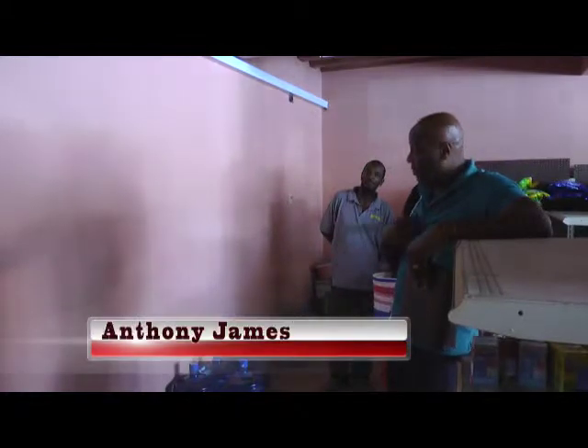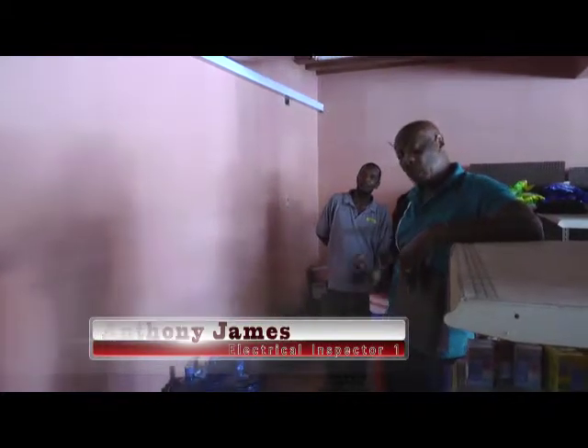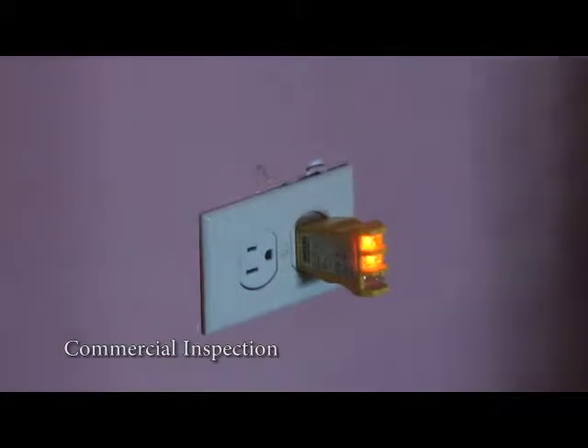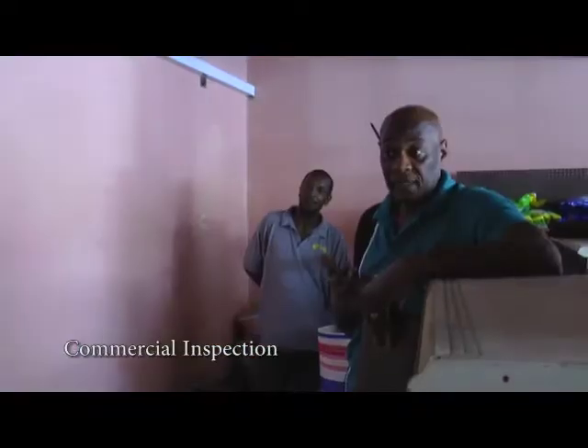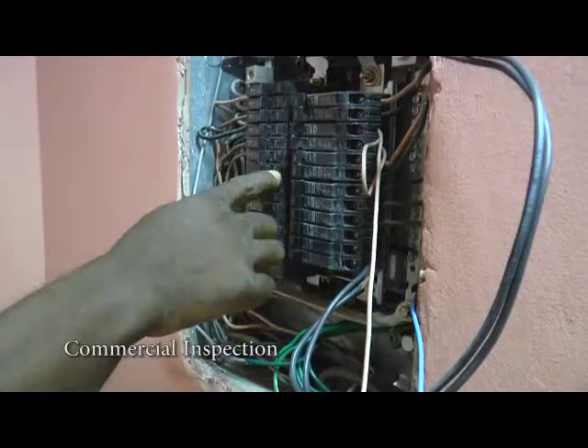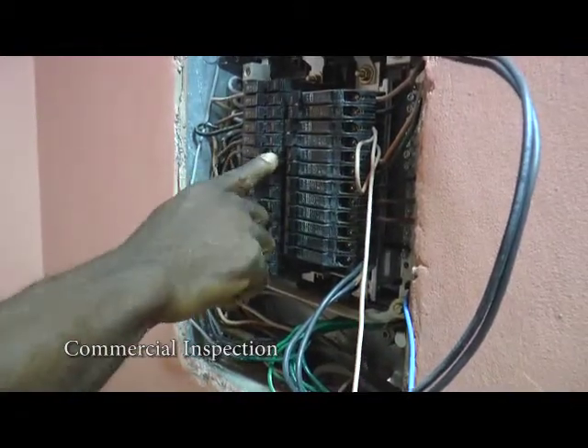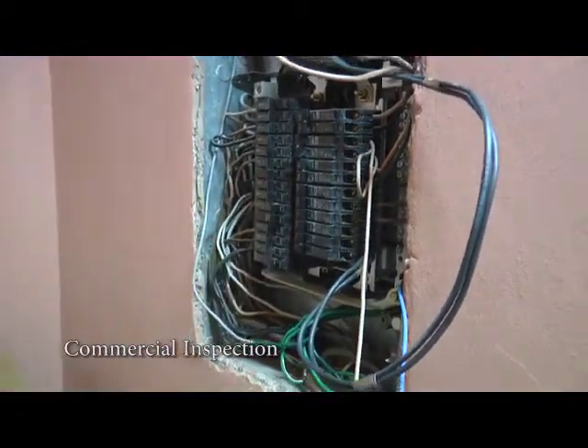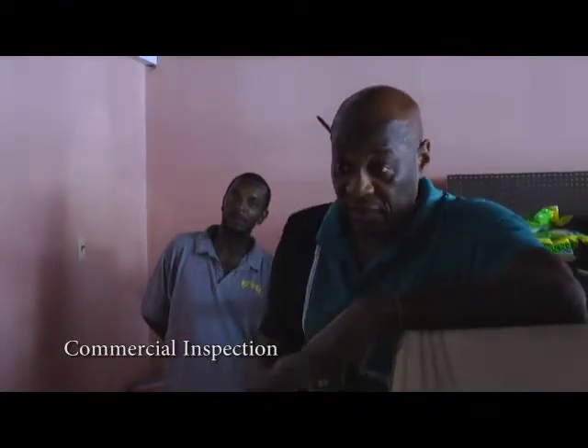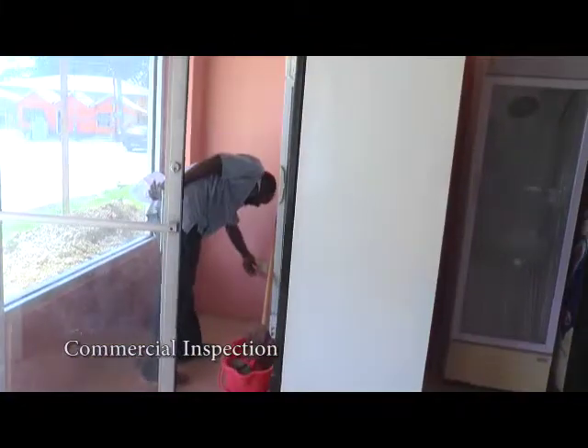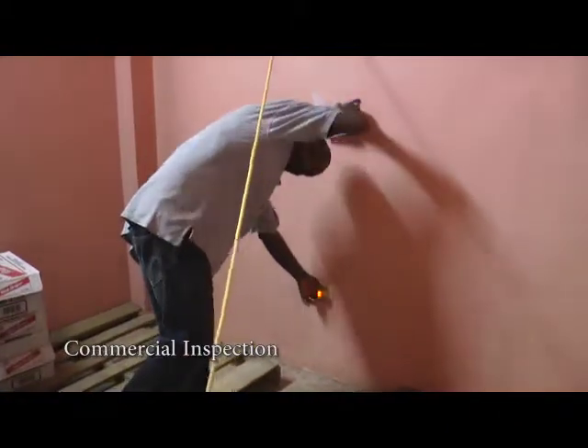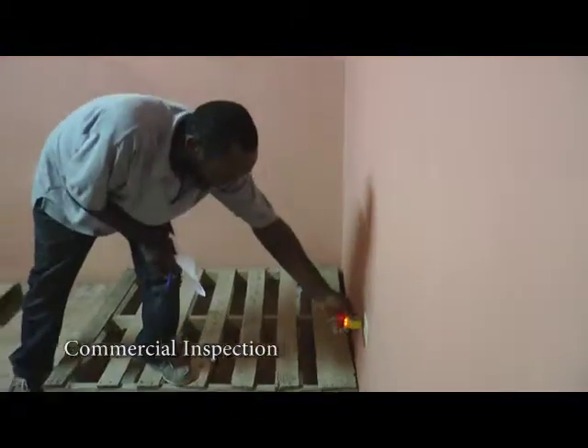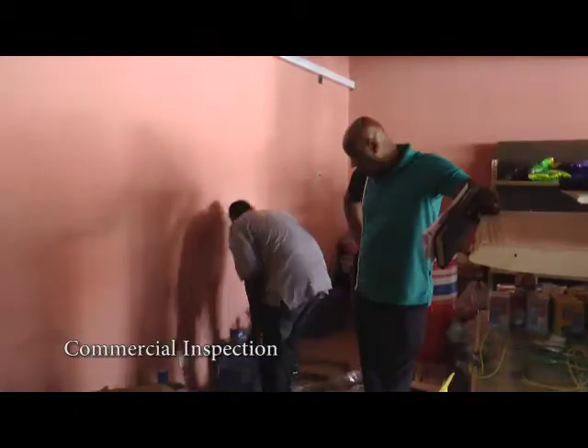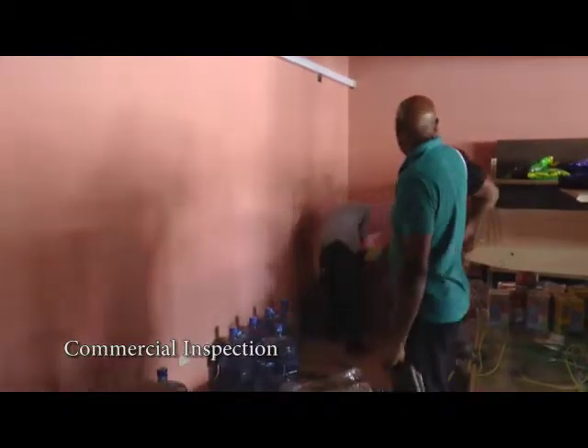This stage of the inspection is where we are testing each individual circuit. Right? The breakers in the panel, each of them control a circuit. So we call them circuit breakers. And what we're doing now is a polarity test. Now the 2 lights will indicate a correct wiring of the wiring device or the socket outlet, what we normally call the plug. So each circuit is being tested individually.